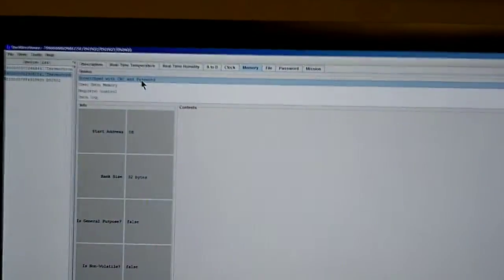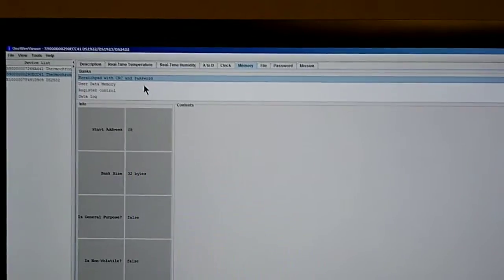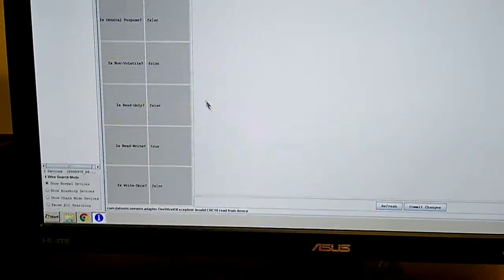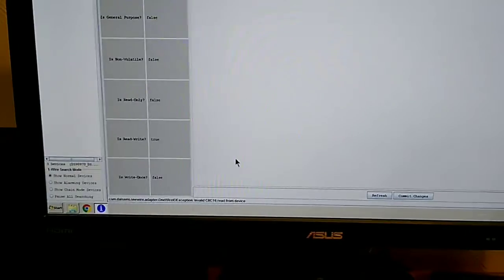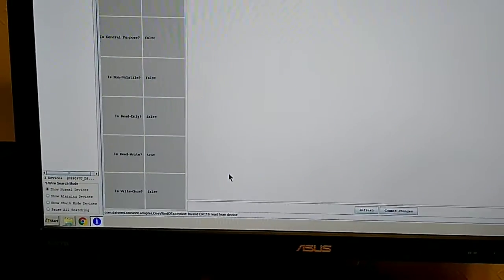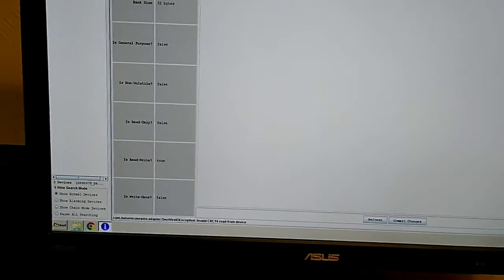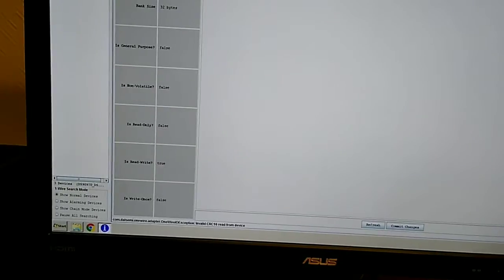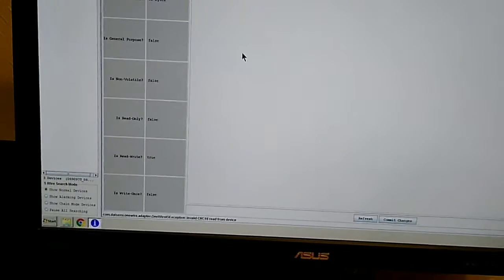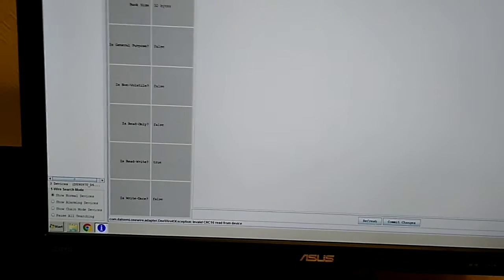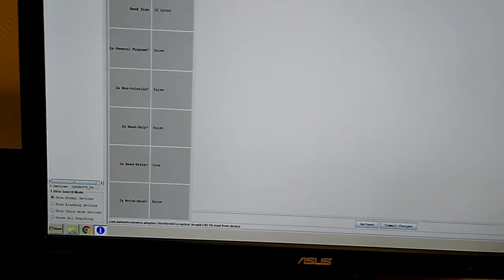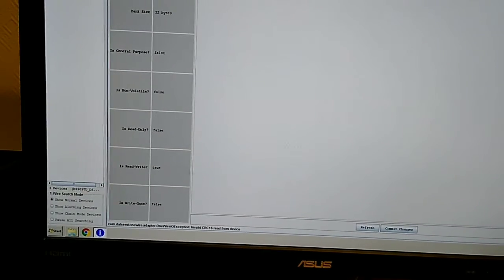You can check whether the problem is the password has been set on the device or the battery is depleted by going into the memory tab here, selecting scratch pad with CRC and password. And then if you still get an error message, it means that the battery is dead because that scratch pad isn't password protected so it should be able to read it even if there's a password on the device.